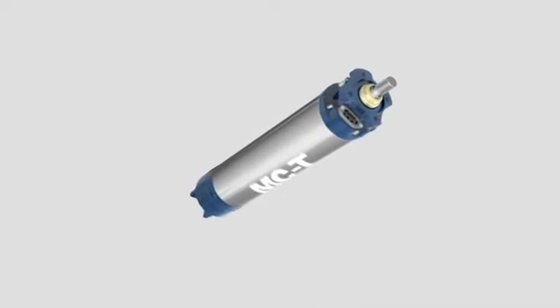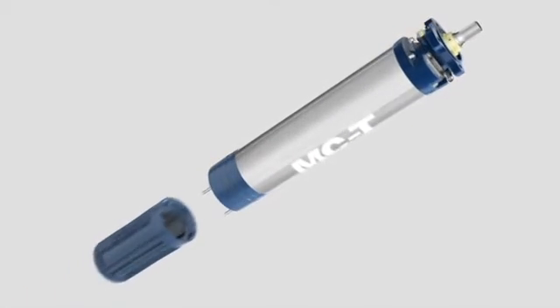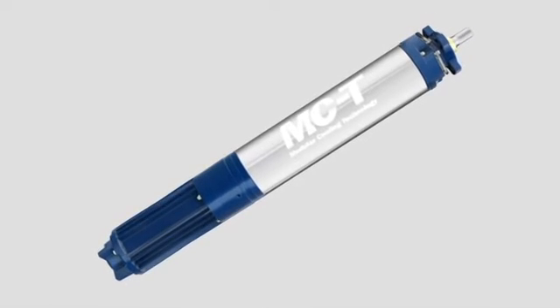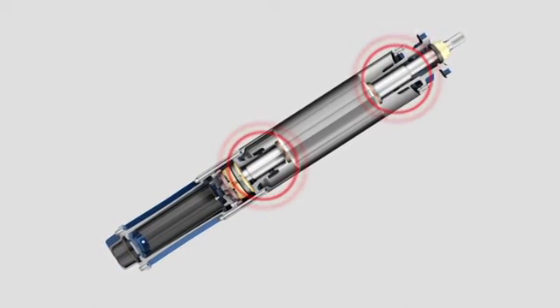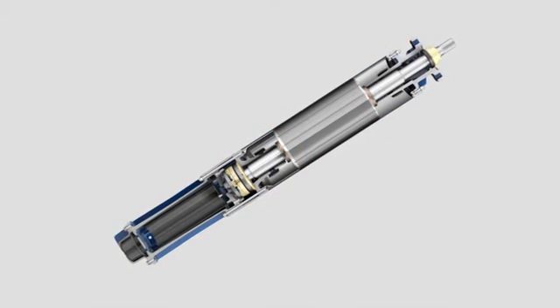Heat exchanger modules can boost cooling performance and above all facilitate customization — that is why we call it modular cooling technology. Windings made of heat-resistant materials increase the technical thermal limits further, enabling motors featuring MCT to be deployed in media up to 75 degrees Celsius.